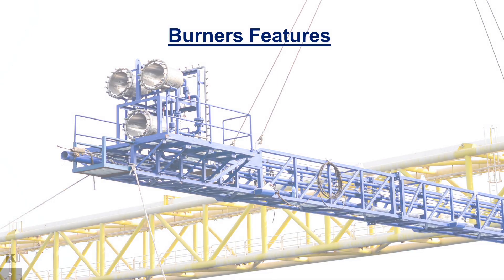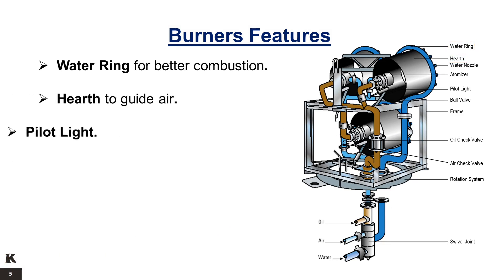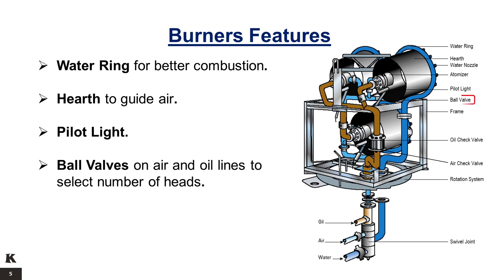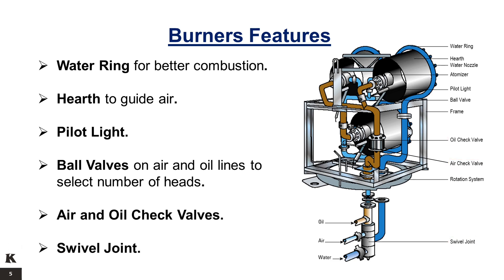Burner Features. Burners are usually equipped with a water ring for better combustion. A hearth is used to guide the air. A pilot light is used to light the burner. Ball valves on air and oil lines are used to select the number of heads to be used. Air and oil check valves prevent air from passing into the oil line and vice versa. A swivel joint allows pivoting position of the burner.